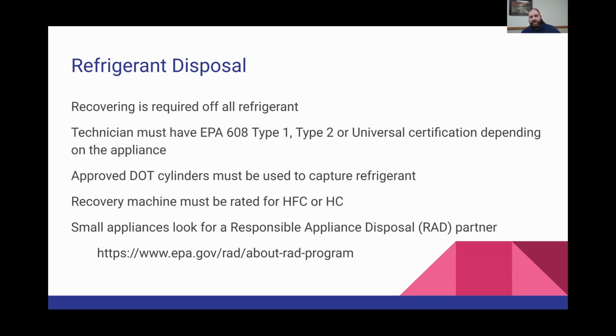Your technician needs to be certified. This right here will be the first time in the last year that anybody besides me has looked at this card, because it's been a year since I opened up a supply house account and had to show them. Right on that little spot that says universal. So what's it say? Has successfully passed a universal exam on how to responsibly handle refrigerant as required. If you're going to work with any of these refrigerants we listed, A1s, A2Ls, A3s, you have to have either Type 1 for small appliances, Type 2 for high pressure and basically anything else, or Universal, which covers Type 1, Type 2, and Type 3.